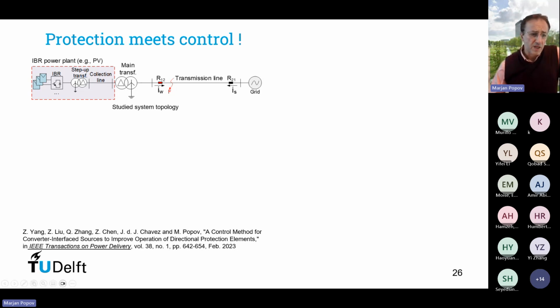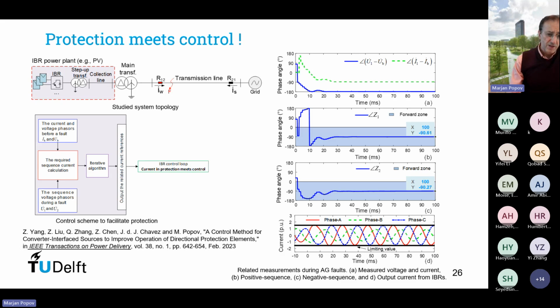For instance, sometimes we can provide different control strategies that will improve the sensitivity of the protection. This has been done in this work published last year. Upon the occurrence of a fault on a transmission line, which is protected by a directional protection, a suitable control strategy provides current limitation and impedance phase angles for the positive and the negative sequence to be minus 90 degrees. This denotes the forward zone.